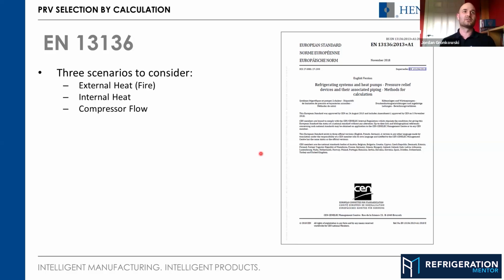So 13136 looks at three scenarios that you size your valve based on. The first is external heat source, which is effectively a fire, by far the most common one that everyone thinks about when they're sizing a PRV.